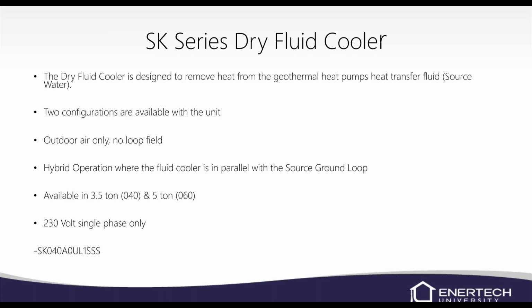In hybrid operation, the fluid cooler is in parallel with the source loop. So maybe they've got a 5-ton loop in the ground and they decided to go with an 8-ton water-to-water unit because they added on to the home and put some radiant in. Instead of putting more loop in the ground, you could add this to the loop. Or if they have problems with their loop field getting too hot or too cold, winter or summer, and it's not quite big enough, then you could add this dry fluid cooler as well.